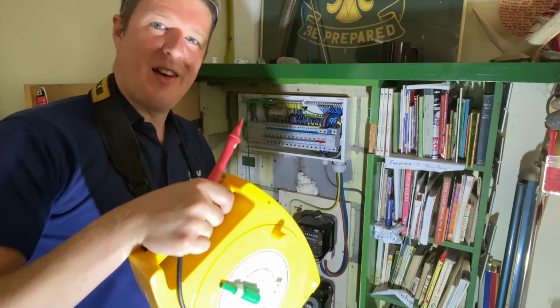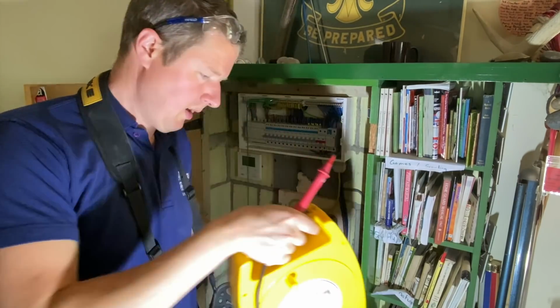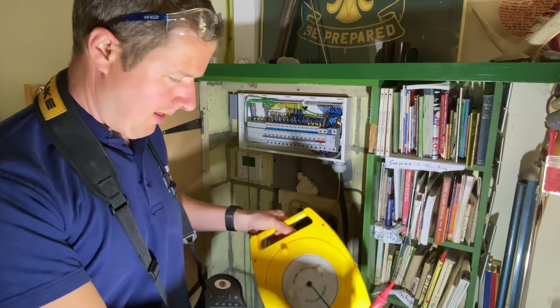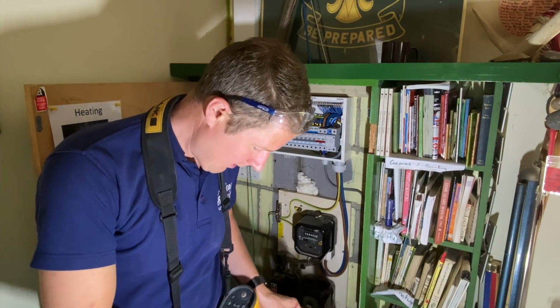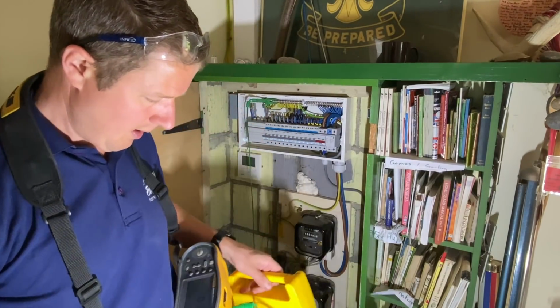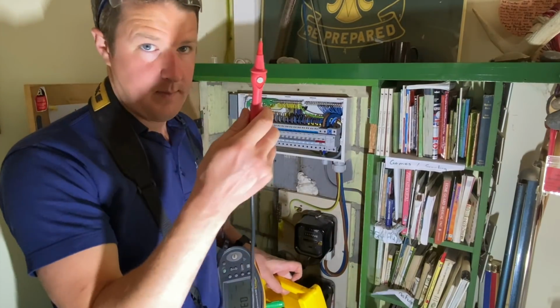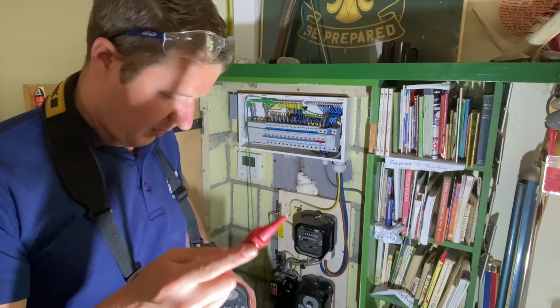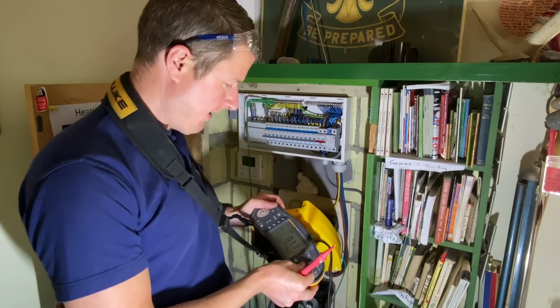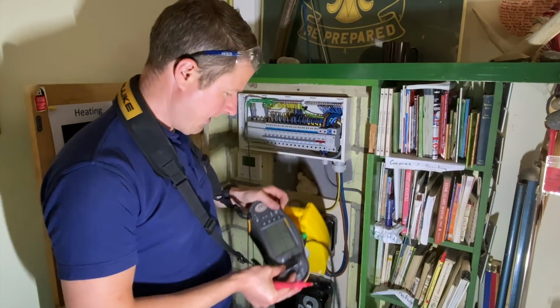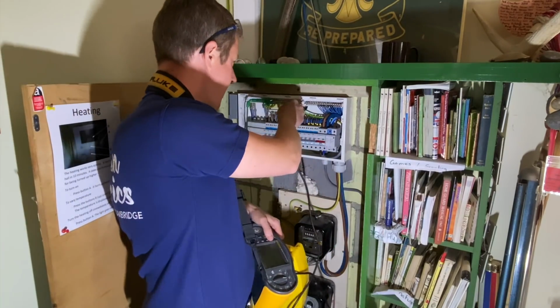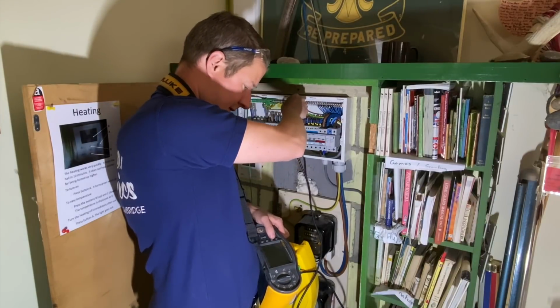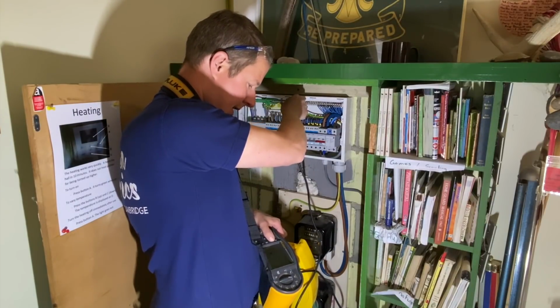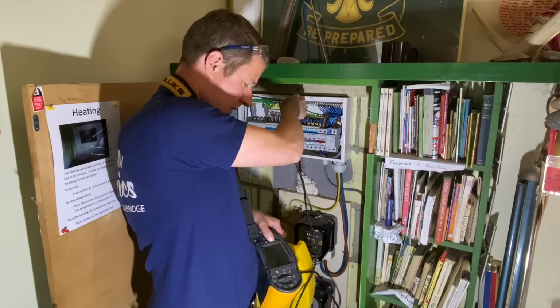Quite a big building, so we do that, and then this end goes into the tester in the earth terminal, and the other one, we use this as our test probe to do the tests. We set the tester to the continuity R low setting, and we have to remember to zero out the leads first because we're increasing the resistance quite significantly on the leads. So we zero out the leads.